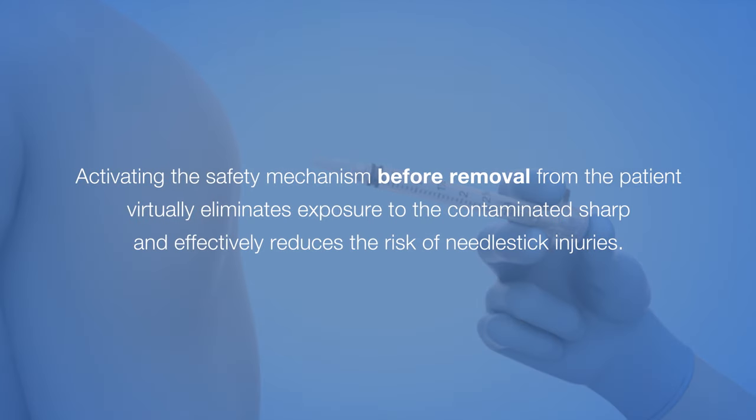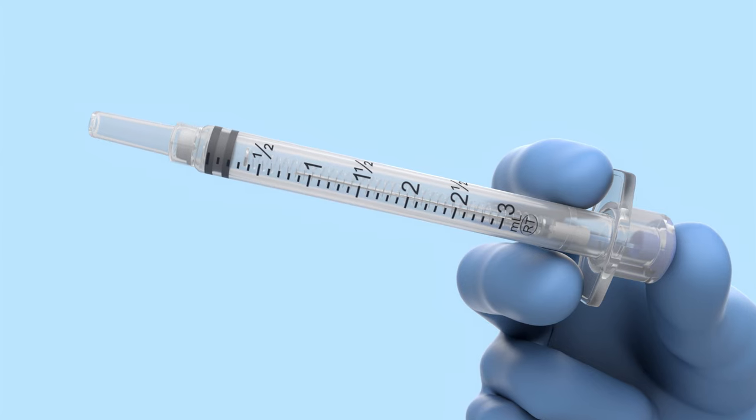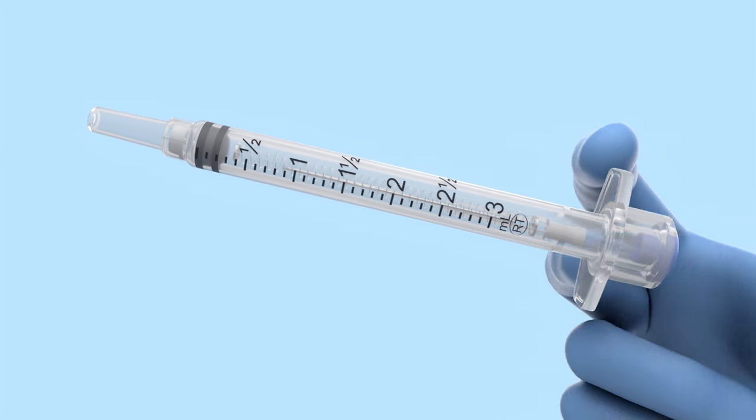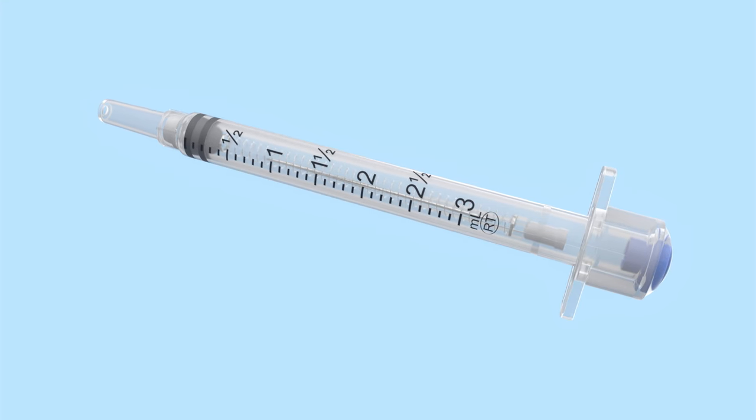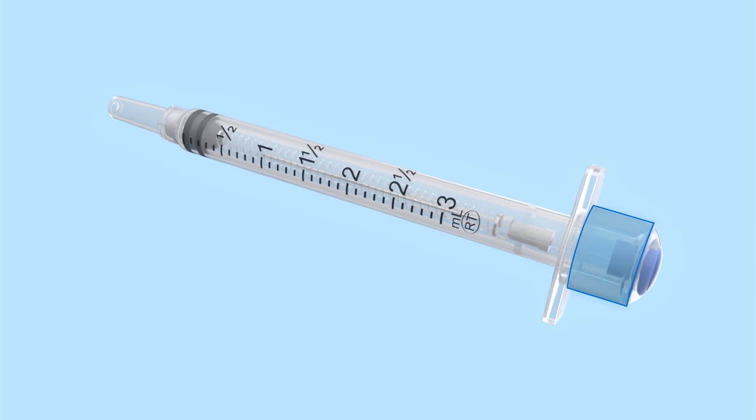Activating the safety mechanism before removal from the patient virtually eliminates exposure to the contaminated sharp and effectively reduces the risk of needle stick injuries. When fully depressed, the end of the plunger handle of 3mL and larger VanishPoint Syringes should be flush with the collar behind the flanges.